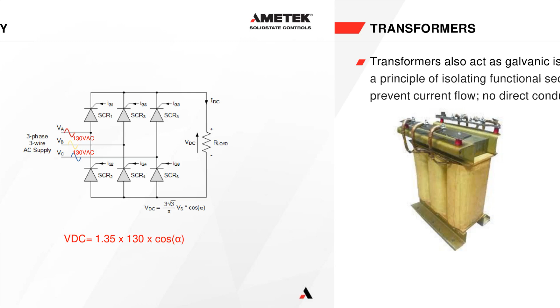Okay. And then I said that there's two reasons. The other major reason is transformers, isolation transformers in particular, also act as galvanic isolation. And that's the principle of isolating the functional sections of an electrical system to prevent direct current flow. In other words, you can see here, we have our primary, and the current will flow through this coil here and magnetize the core there, but no current, direct current, flows from these cables over to these cables here. It's magnetically induced. So the magnetic field in here will be induced over here as well, and therefore you can have current flow on the output. But there is no current flow from this cable here all the way over to this cable here.